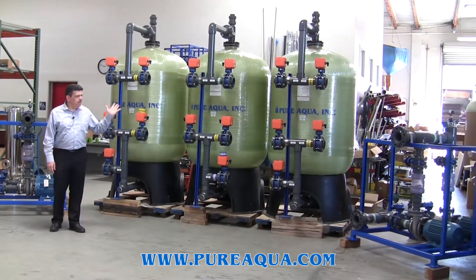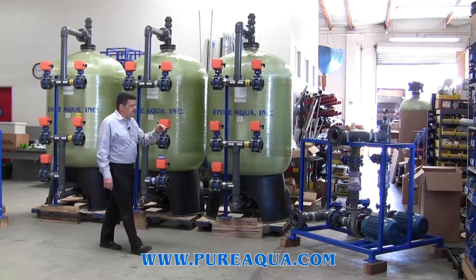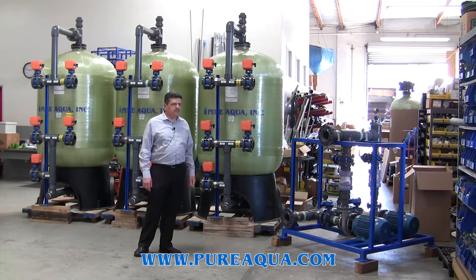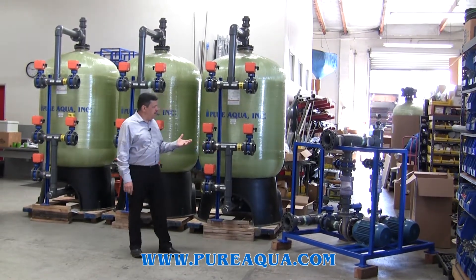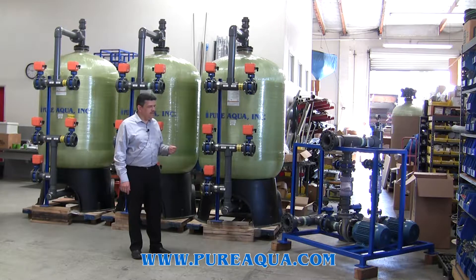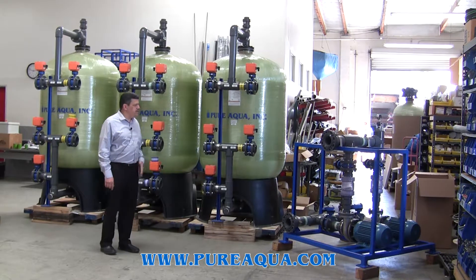As we see here, we start the system with a feed and backwash pump. Those pumps are made of duplex stainless steel alloy, which is one of the highest non-corrosive materials — they resist corrosion in the water. Seawater is very corrosive due to the high TDS or salinity and the warm water, which causes a lot of problems if you are not using the correct materials.